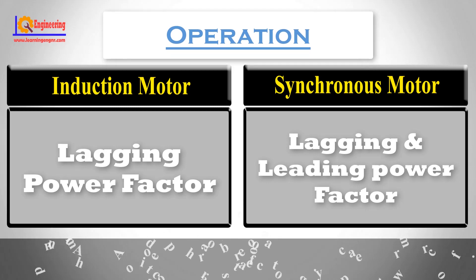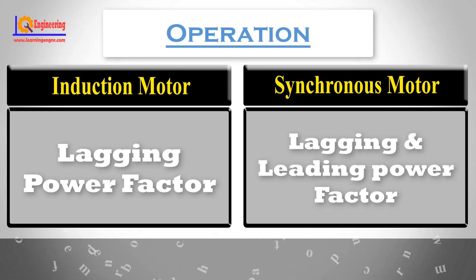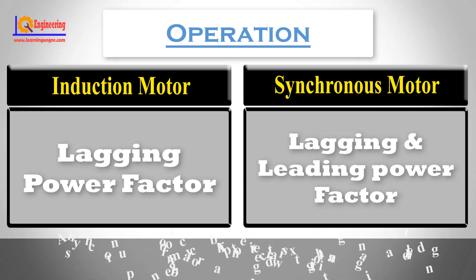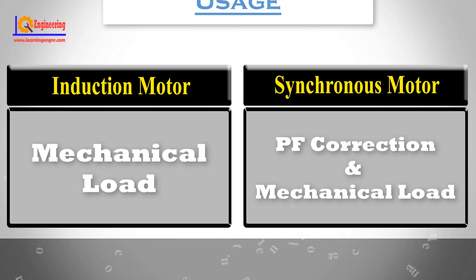An induction motor operates only at a lagging power factor, and at high loads the power factor becomes very poor. A synchronous motor can be operated with lagging or leading power factor by changing its excitation.